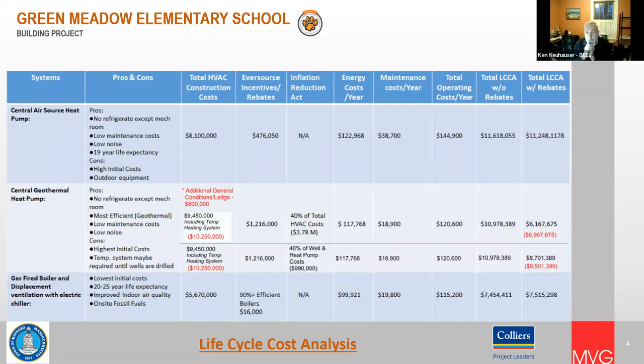Are you aware of a heat pump technology that can heat water that high? No. So the heat pump water distribution would be slightly lower than that — maybe a bit more active fin on the fin tube for each classroom, that type of thing, but pretty minor adjustments between the two. Okay, right. So for example, with a ground source heat pump, we really want to keep that around 110. If it were to switch over, we'd need some change on the infrastructure, or maybe there's a different technology available by then.